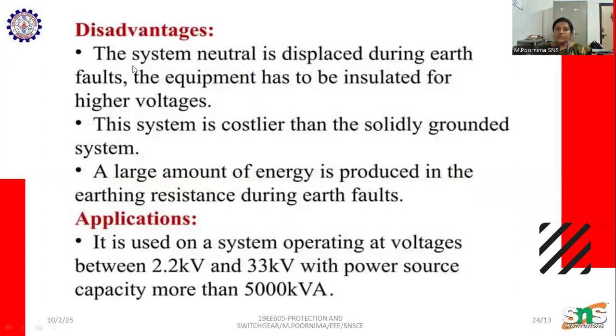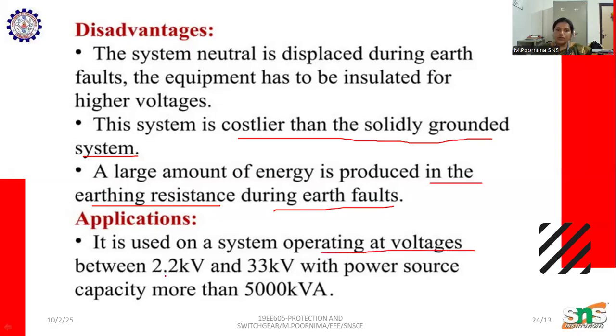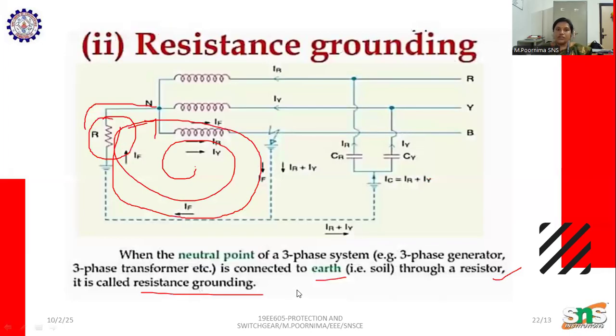The disadvantages are that the system neutral is displaced during an earth fault, the equipment has to be insulated for high voltages, and the system is costlier than the solid grounding system. A large amount of energy is produced in the earthing system during the fault. As for applications, it is used on systems operating at voltages between 2.2 kV and 33 kV with power source capacity of more than 5000 kVA. So these are the advantages, disadvantages and applications of resistance grounding.